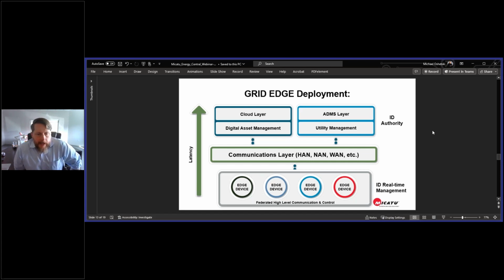Those edge devices are now federated. What I mean by federated is having grid edge processing actually in each device. So let's think about a distribution grid—a typical transformer and substation. Let's say we have 6 feeders, and each feeder has 6 to 7 edge control devices with sensing. So we have approximately 36 sites that we're actually measuring from.